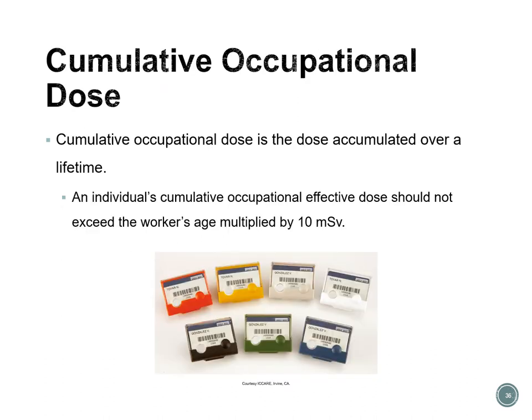The cumulative occupational dose is the dose accumulated over a lifetime. An individual's cumulative occupational effective dose should not exceed the worker's age multiplied by 10 millisieverts. For example, if the worker is 60, then 60 times 10 equals 600, so the individual should not have been exposed to more than 600 millisieverts in their lifetime. To begin working with radiation and become certified, you must be at least 18 years old.